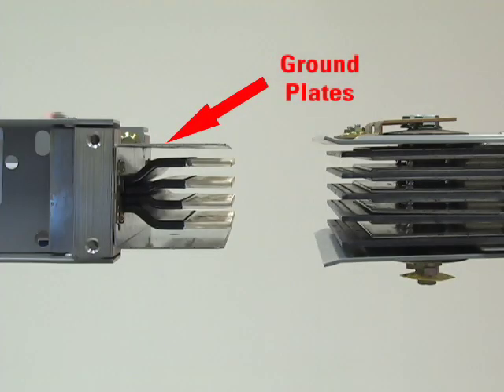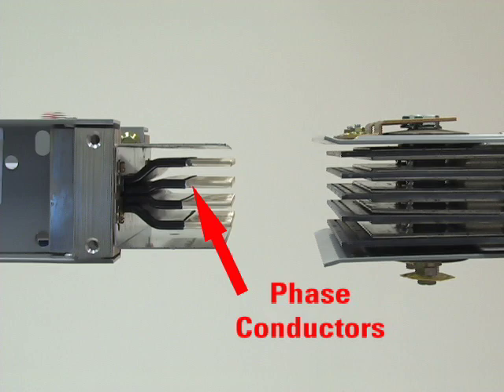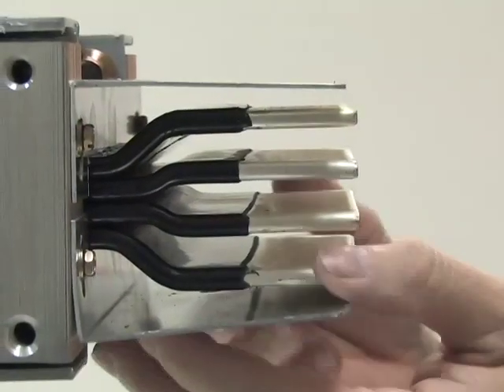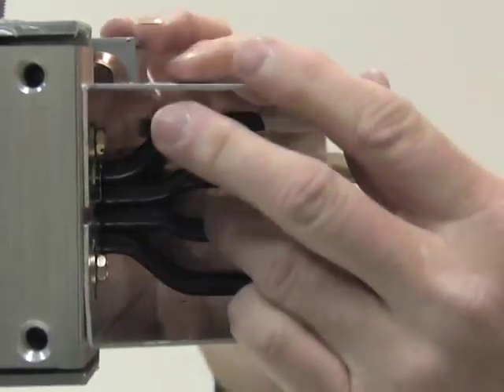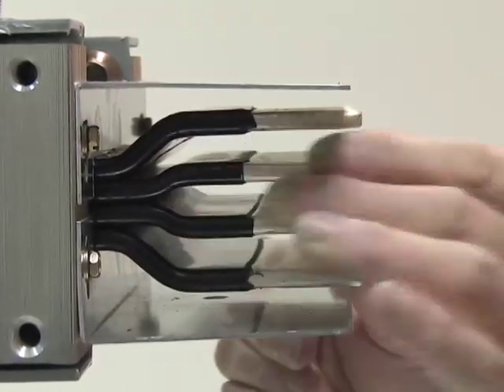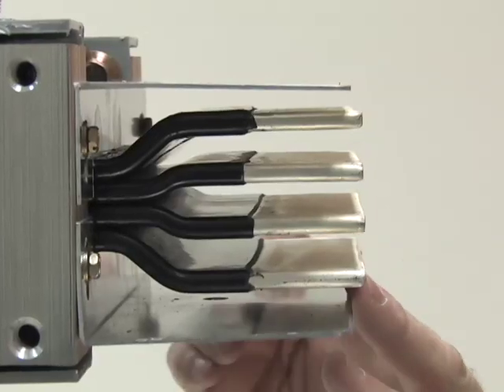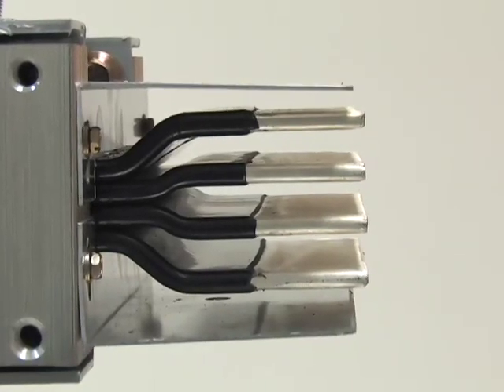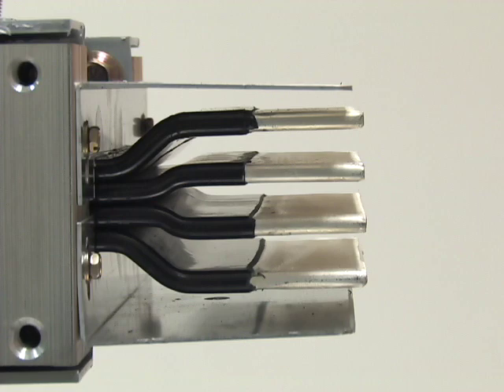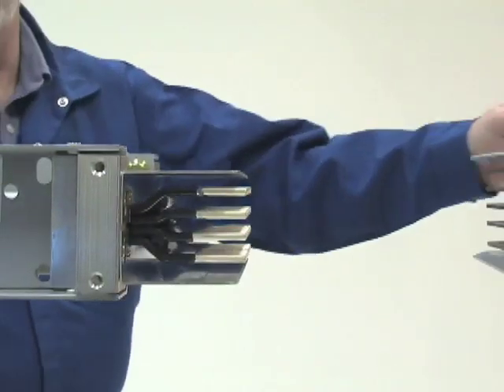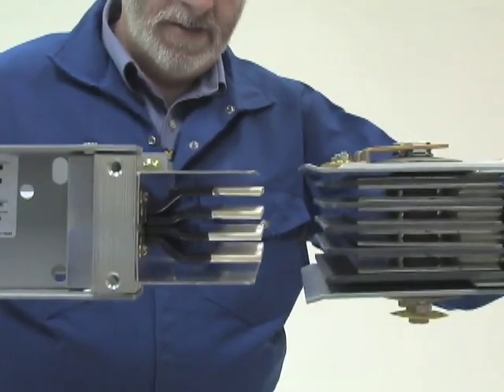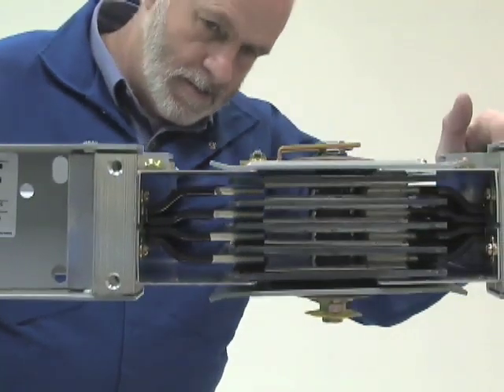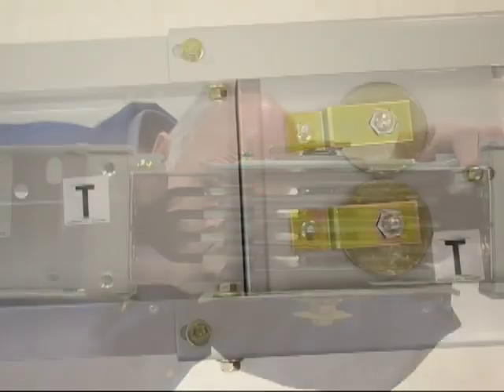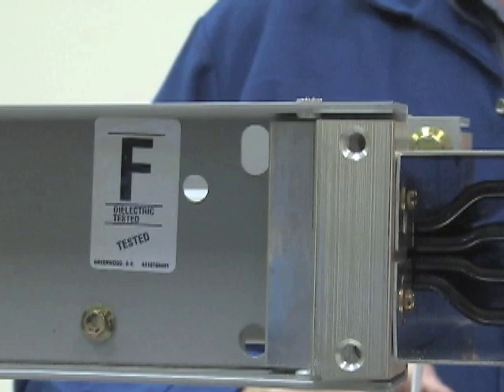When connecting pieces of the BUSWAY 3 busway together, make certain that contact surfaces are clean and free from contaminants. Some sections may have electrical lubricant on the contact surfaces which was applied by the factory. This will aid in joint installation. To begin the joint installation, first align the left end of one section to the right end of the adjoining section with the T and F labels in alignment.